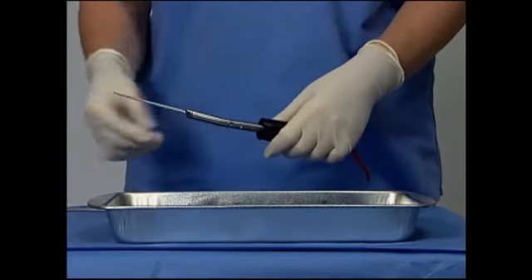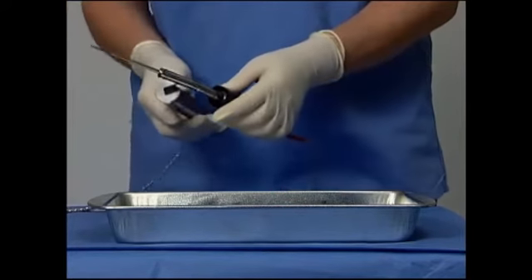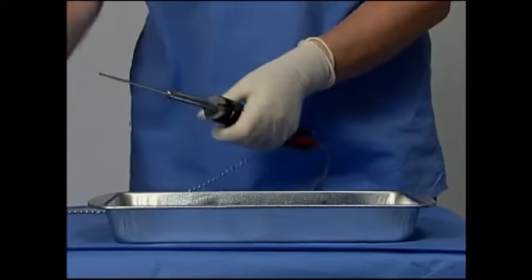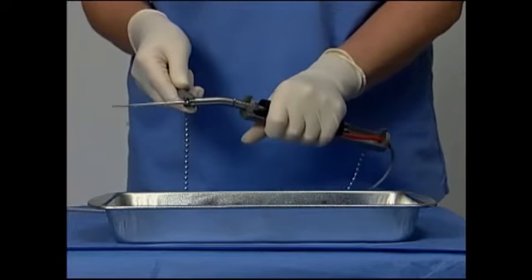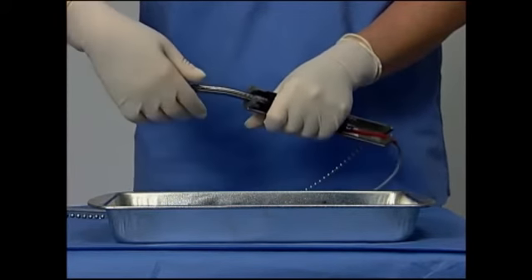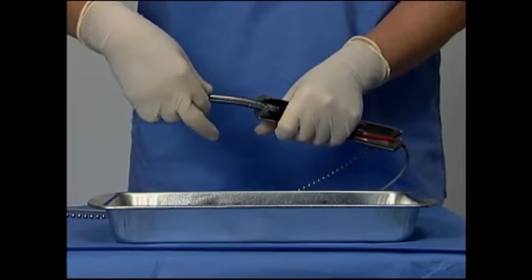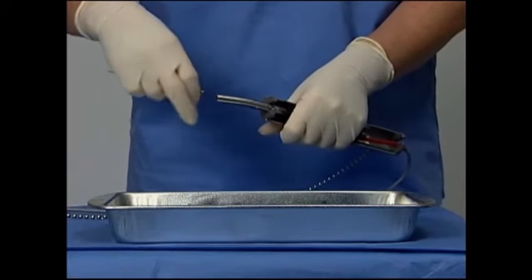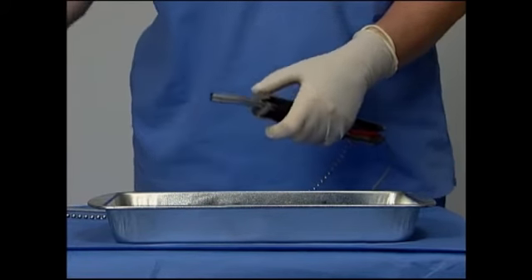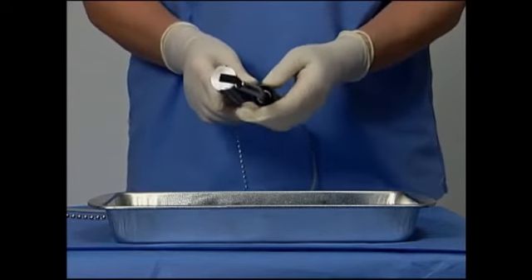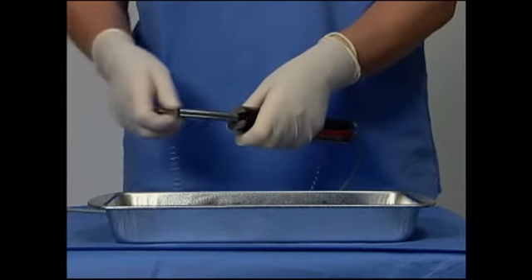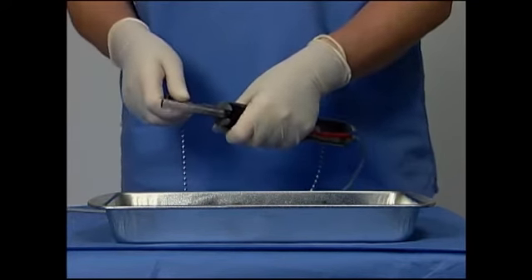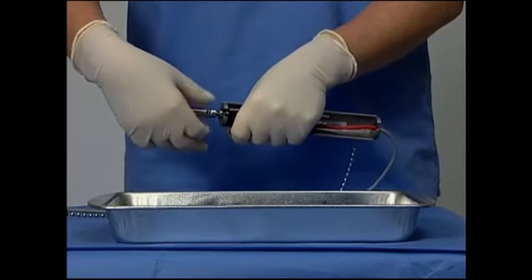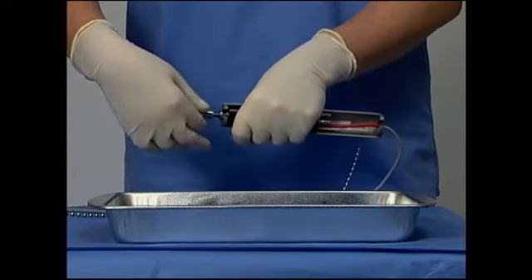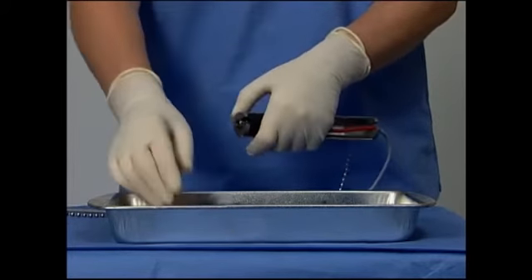Using the appropriate wrench set, place flat 1 of the handpiece in the appropriate sized slot of the holder. Using the appropriate sized end of the wrench, loosen the tip by turning it counterclockwise. Unscrew the tip by hand and discard it if applicable. Reposition the handle of the handpiece and secure flat 2 in the appropriate sized slot of the holder. Using the wrench, loosen the angled extension by turning it counterclockwise. Detach the angled extension and place it in the cleaning solution.